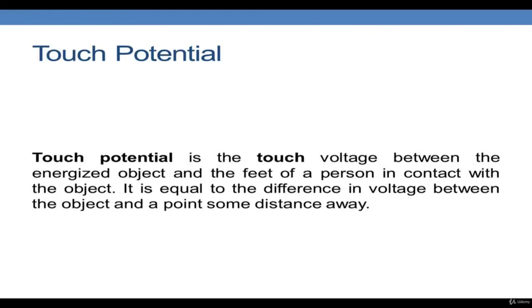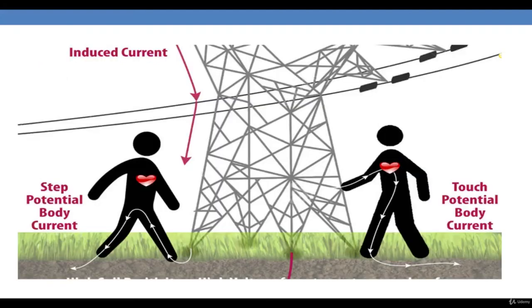And next is the touch potential. Touch potential is much simpler than the step potential. Touch potential is the touch voltage between the energized object and the feet of a person in contact with the object. This is equal to the difference in voltage between the object and a point some distance away. So let me show this graphically. The transmission tower will have induced currents flowing through it. On my right side we have a person touching the transmission line. This is the touch potential from here to here, that is, from the point he is touching with his hand to his feet on the ground. The voltage between these 2 points is called the touch potential.